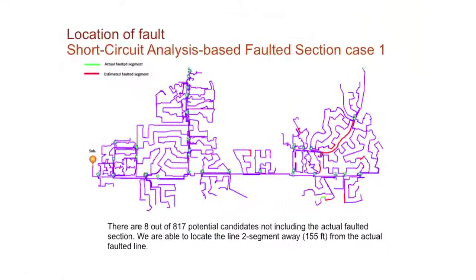And here are just two cases. What you had was our algorithm actually showing and delivering these red lines, based on the fault data. Our algorithm in the Station Computer Com 600 said, I think it's at this segment, that segment, this is all the red. And that segment, and that's actually where it was. Green is where it was. We're within one segment, 155 feet.